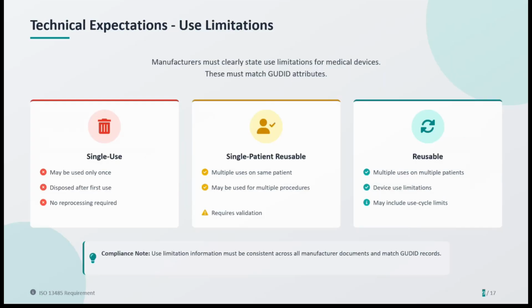Now there are use limitations which are often overlooked. Manufacturers must clearly state whether something is single use or reusable. Single use, as most of you know, means one use and discard. But the IFU can specify that it is single use but patient reusable, which means the item may be used multiple times on the same patient, and in most cases does require sterilization between uses.